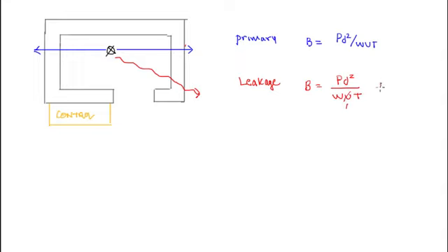But the use factor is 1 because the beam is always pointing at every wall for leakage. So leakage, kind of by design, is less than 0.1% of the workload of the linac, so you can use that too. And so you can rewrite it like this. This is usually how it's written. So 0.1%, 0.001 times W times T.